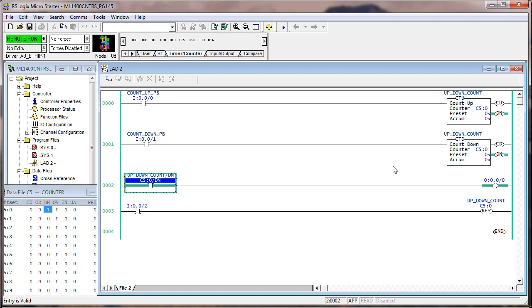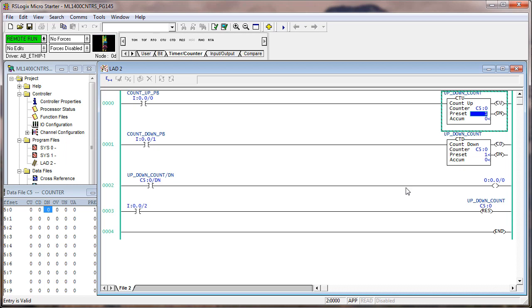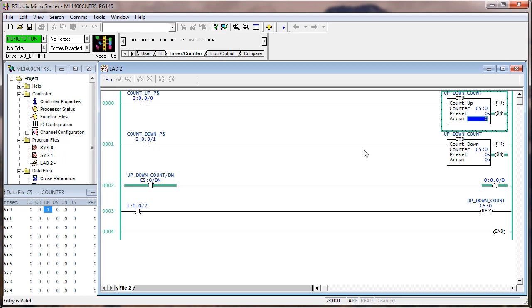When the rung goes from false to true — we didn't do this in the lab, but I'll demonstrate here. I'm going to change the preset to one. The done bit went off because the preset and accumulate are no longer equal. If I set the accumulate to one from the keyboard — not in the logic — the done bit goes back on. This is an important characteristic: you can manipulate these values from other places in the logic. A rung could move a value into the preset or accumulate, and C5 colon zero just responds.